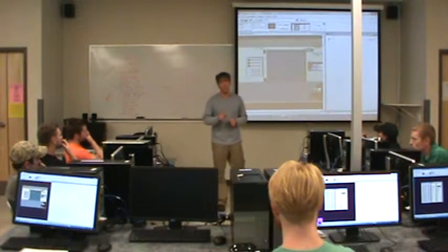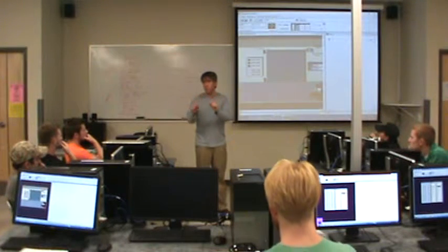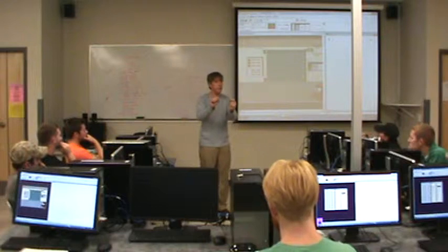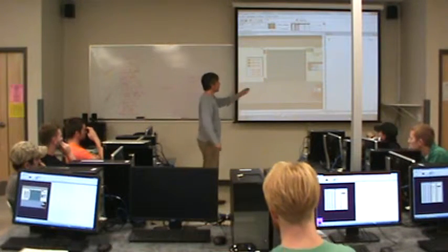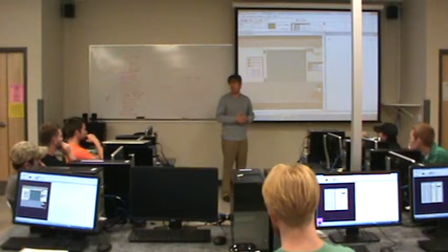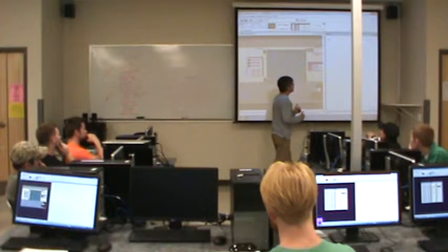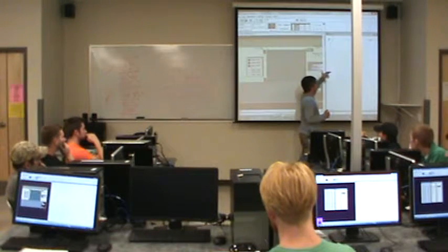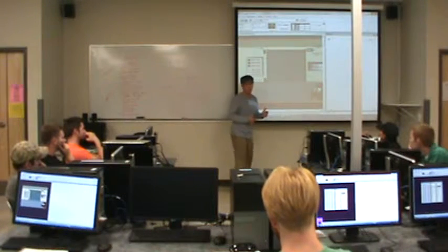The other main difference is that in most languages, you control the program flow. You tell it, go here, now do this, wait till this happens, and then do this. In ladder logic, you can do that, but that's not really the natural way of programming in ladder logic. What you have to think about most of the time is that the ladder is being evaluated and run through over and over.